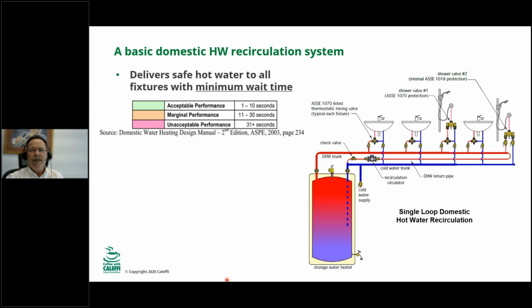And when we talk about wait time, what does it mean to us as individuals? If you are using a lavatory sink in an airport, you don't want to wait more than a couple of seconds for warm water. Maybe if you're going to take a 5-minute shower, 15 or 20 seconds is acceptable to you. So there's no hard and fast rule, but we do have some guidelines here. So when we're talking about time, that's a good reference.